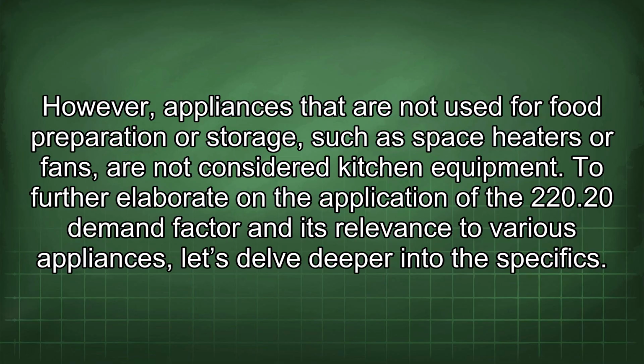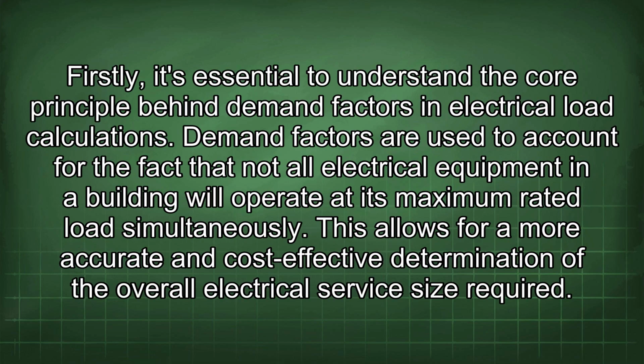delve deeper into the specifics. Firstly, it's essential to understand the core principle behind demand factors in electrical load calculations. Demand factors are used to account for the fact that not all electrical equipment in a building will operate at its maximum rated load simultaneously. This allows for a more accurate and cost-effective determination of the overall electrical service size required.